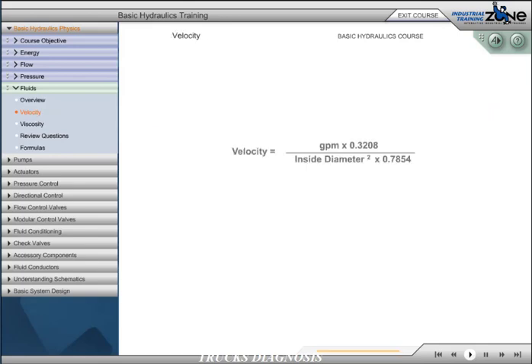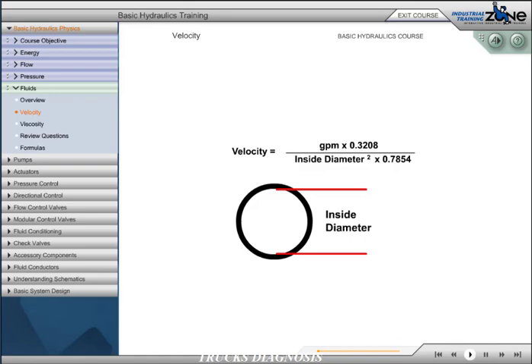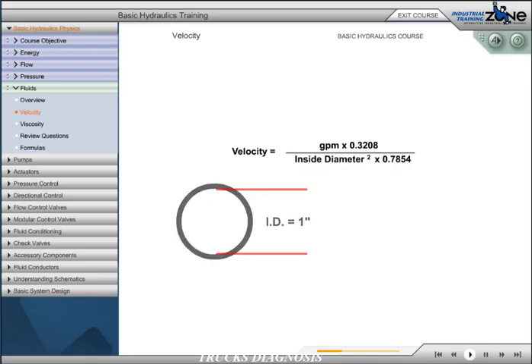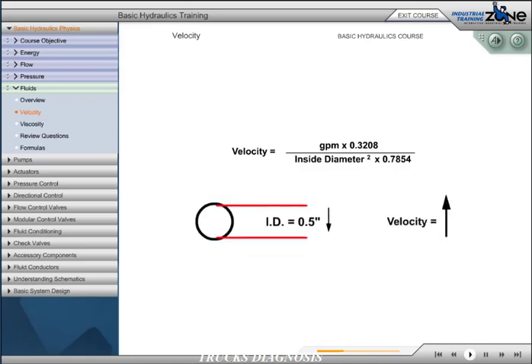Velocity is the distance of fluid travels per unit of time. With a fixed volume of fluid going through a conductor, the velocity of the fluid will depend upon the inside diameter of the conductor. If the diameter of a conductor is increased, the velocity of the fluid will decrease. Conversely, if the diameter of the conductor is decreased, the fluid's velocity will increase.